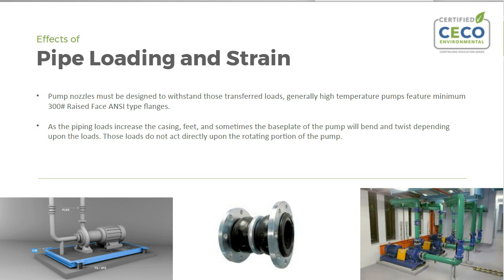You can see in this photo on the lower right-hand side of the picture, that's just a standard centrifugal pump, but the suction and discharge both have flexible members that keep those forces, moments, and loads separate from the pump itself. It gives room for that pipe to expand, and allows the piping to move while keeping the pump stationary without putting exceptional loads onto the nozzles of the pump.